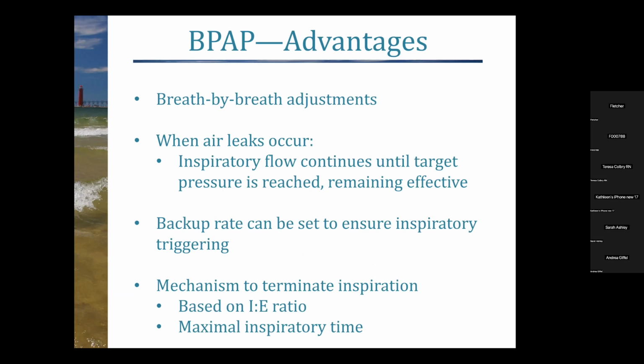Again, it can do breath by breath adjustments. So it's triggering based on what the patient is doing and breathing. Because it's set to meet that certain pressure, if there is an air leak around the mask, it's going to continue to increase that pressure until it meets that target pressure. So we get that continuous flow. And we can also set a backup rate. So if the patient is not triggering breaths after a certain amount of time, it will trigger those breaths itself. And then there are also mechanisms to terminate inspiration. So those of you in the room can't see this because of the bar in the way, but there's an inspiration expiratory ratio. So you set that on the machine. So after a certain amount of time of inspiration, it'll automatically start the expiration process.